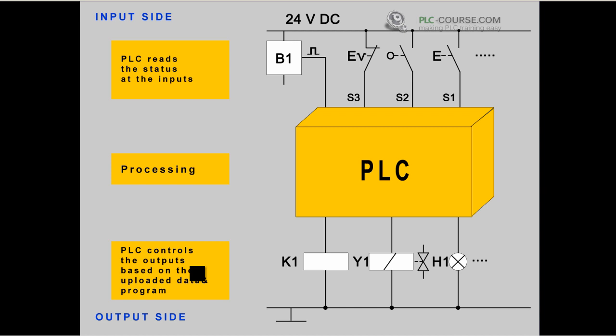Now here is an example of a common error. When we start our program, the PLC reads the status of all the inputs and outputs and decides that it is safe to open the gate and it is safe to close the gate, because at this point nothing has happened yet. We move to the second stage of processing and ask the program to open the gate. The program begins to open the gate, but PLC does not go back from this stage to store a piece of information that the gate is now being opened.